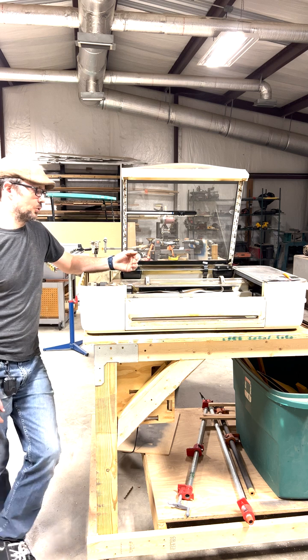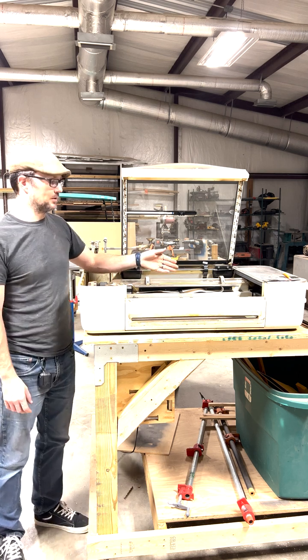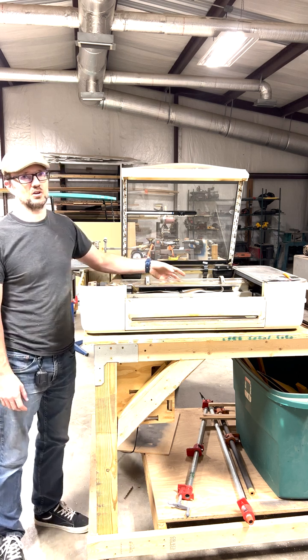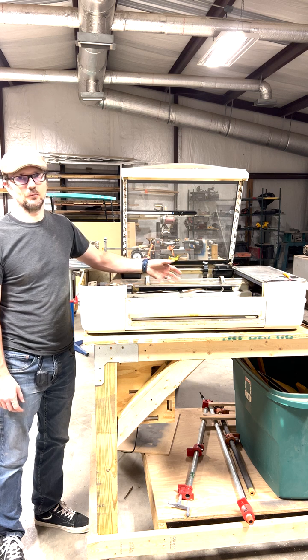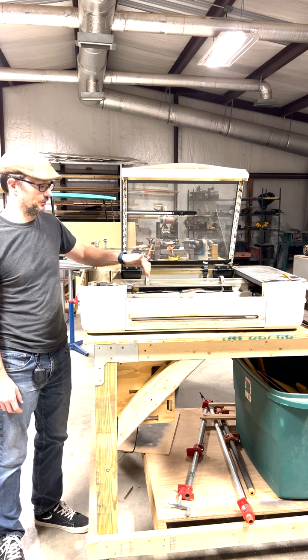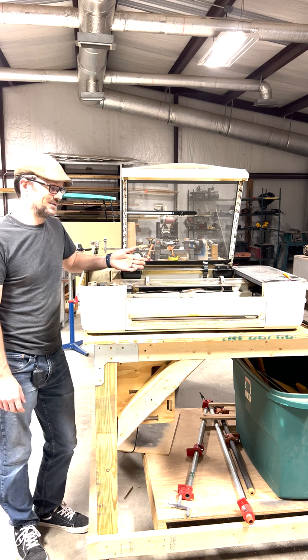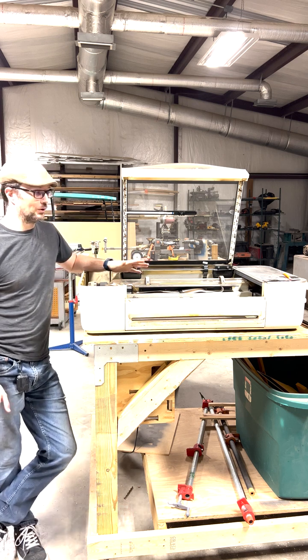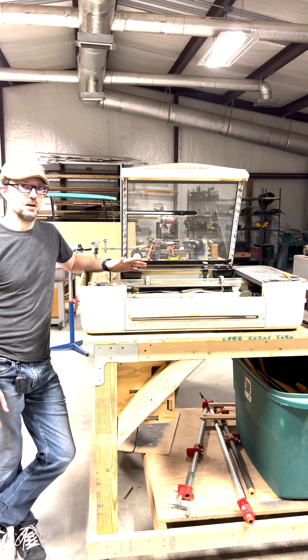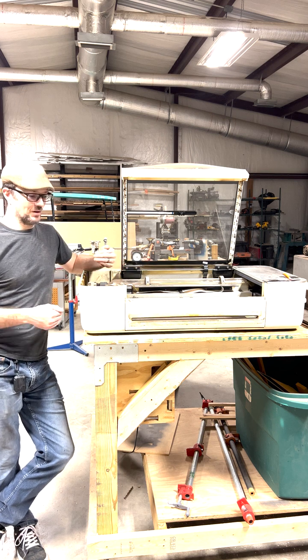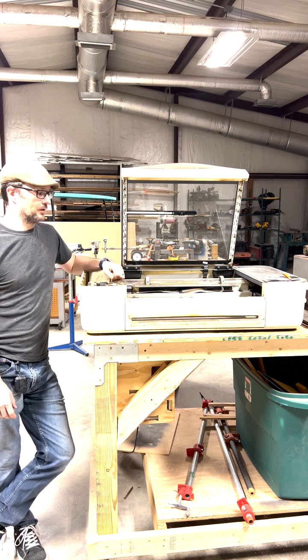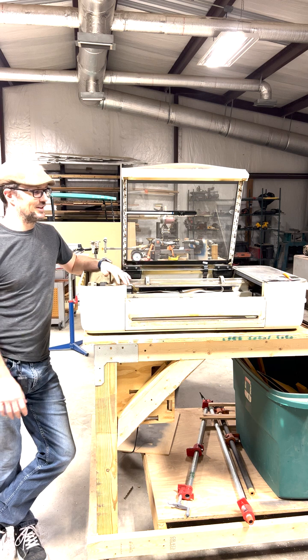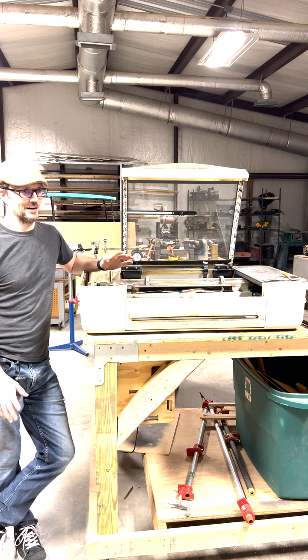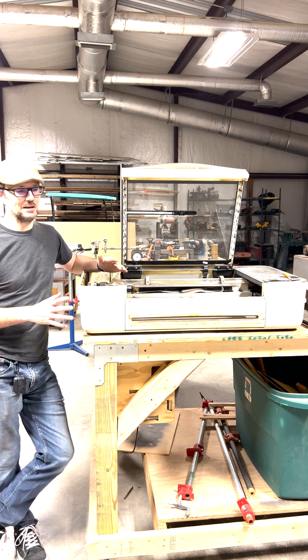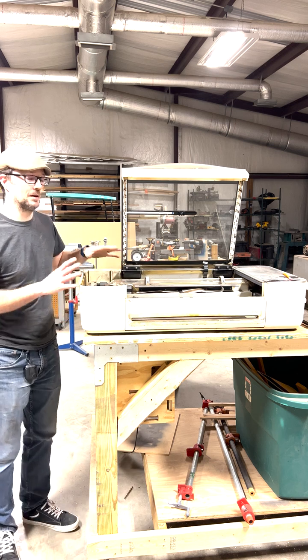So we've come to the conclusion, looking at it, that a mix of rubbing or moisture getting on it has caused them to arc and jump out of the insulation and into the grounding of the machine. When that happens, you're done. The machine moves like normal, but you get no laser beam. So I've walked a ton of people through how to repair this, and there have been some videos on how to do it, but today I decided to make a video to make it easier and more comprehensible for people to be able to do it.